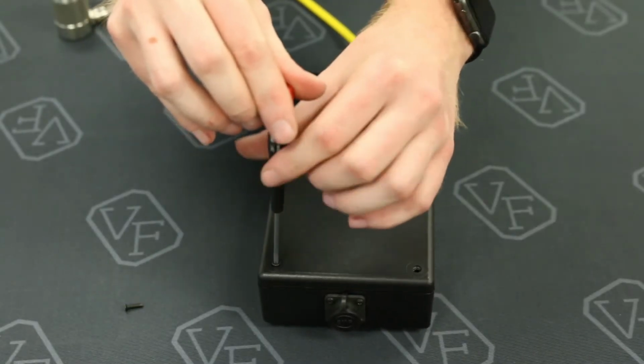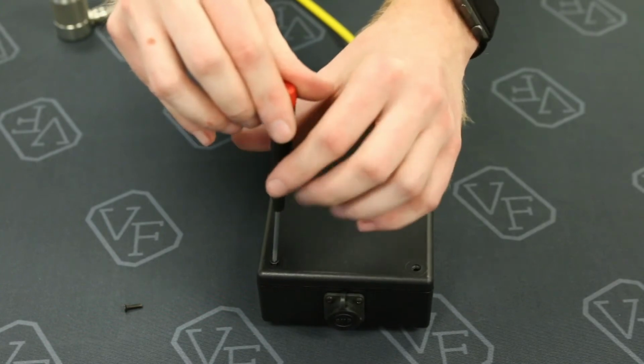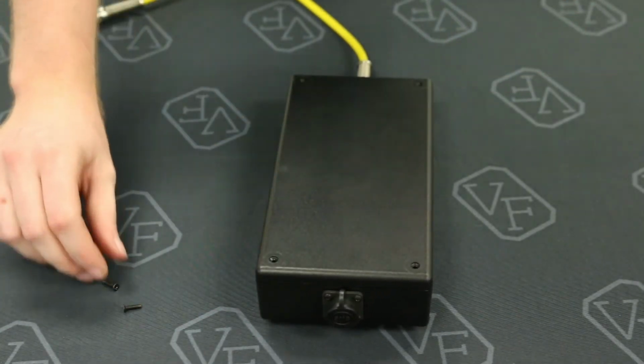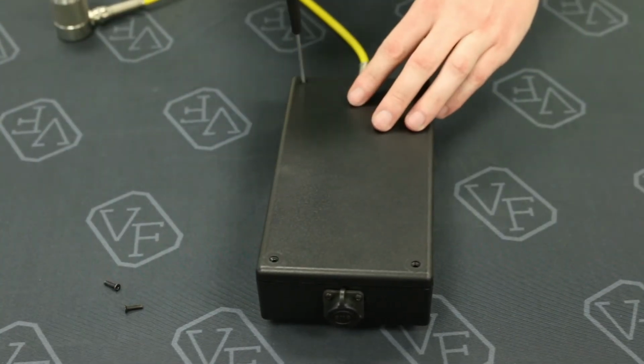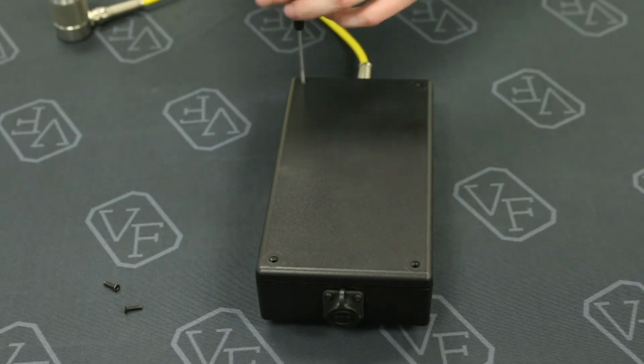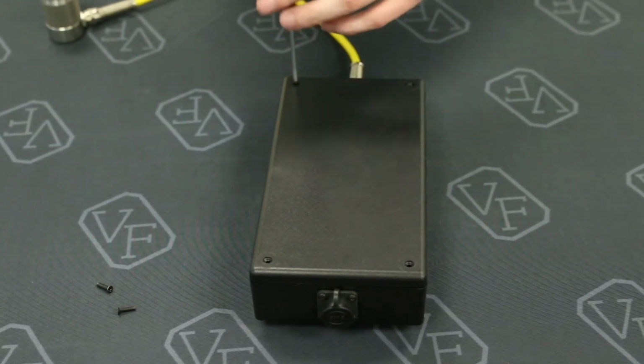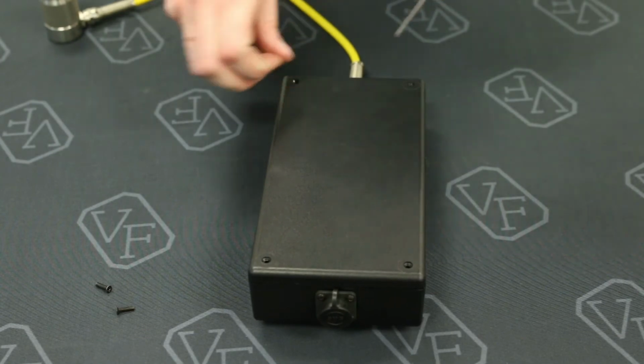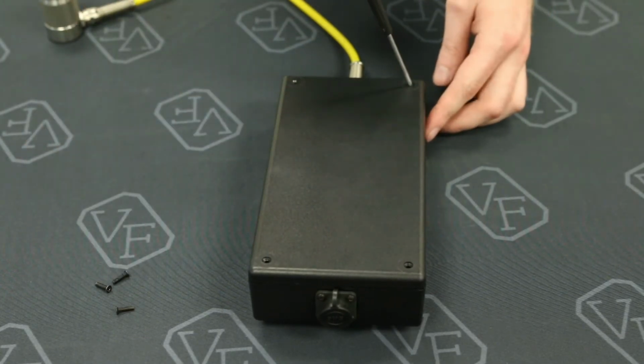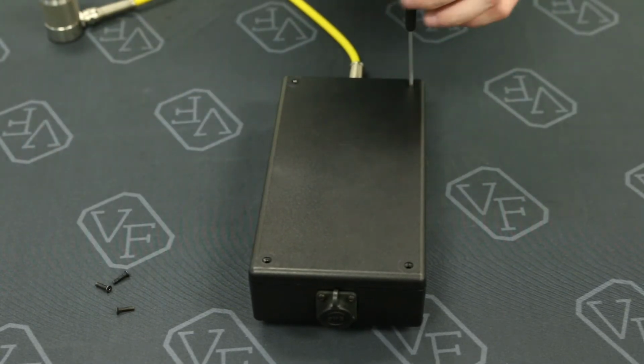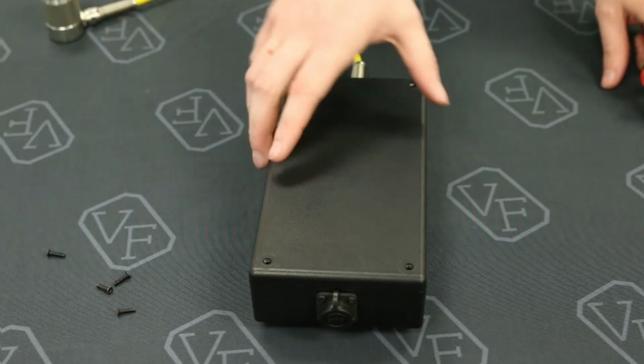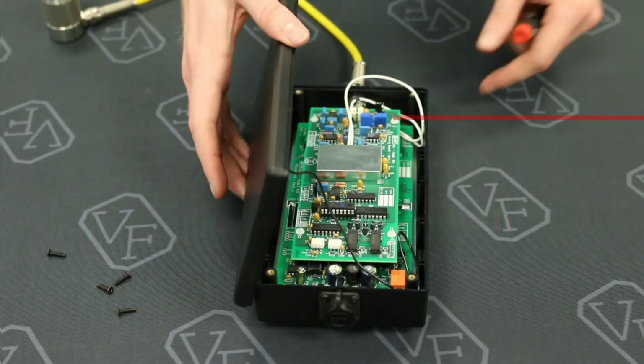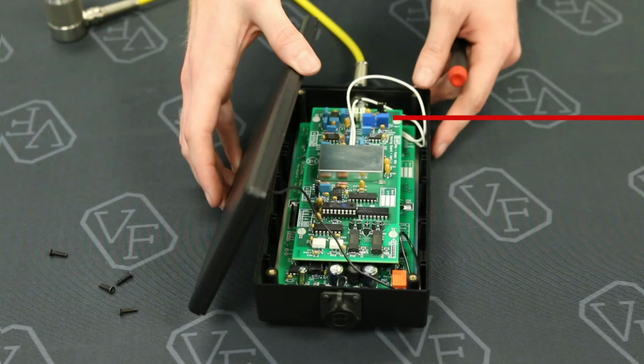If calibration is required, bring the 424A to a clean workbench. Remove the 4 enclosure screws found on the back of the unit. Carefully remove the rear of the enclosure and use caution to not inadvertently touch any internal components found inside the 424A unit. 2 blue potentiometers can be found inside the 424A enclosure.